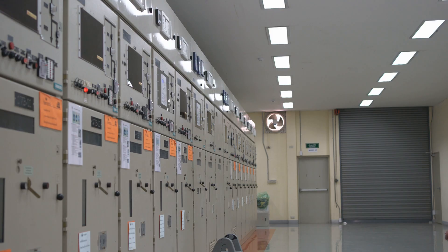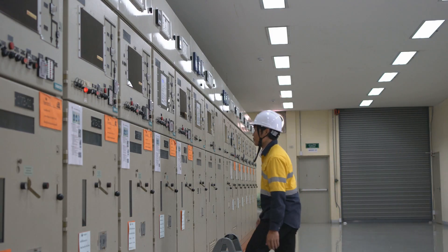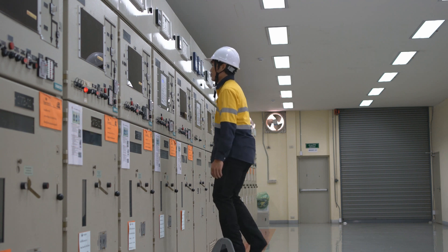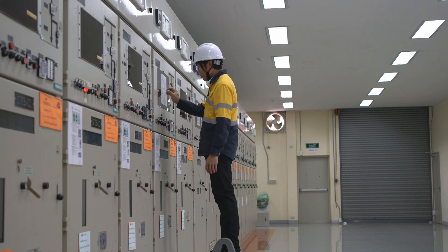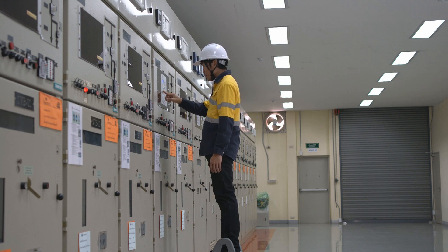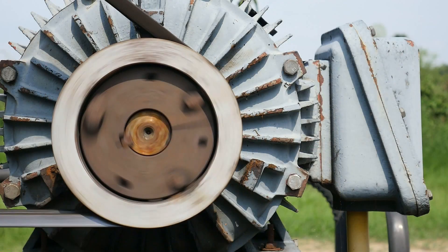This creates 10 additional paths for earth fault currents, complicating fault detection. With so many paths for fault currents, protection relays may fail to detect the correct fault location, causing nuisance trips and incorrect relay operations.